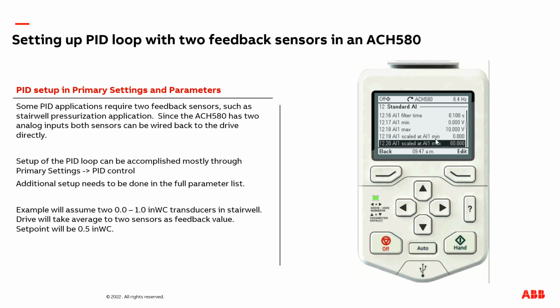Here you can see we have our scaled analog input min is 0, which is what we want, but our max is 60. We want to edit this to 1.0. Now, if you have a transducer, for example, let's say that's -1 to +1 inches of water column, you would want to make adjustments here. For example, on AI1, you'd want to make this, for example, -1. So that when you have 0 volts, that would correspond to -1, and you had 10 volts, that would correspond to +1. In our example, we have 0 volts corresponding to 0 inches of water column, and 10 volts is corresponding to 1 inch of water column.